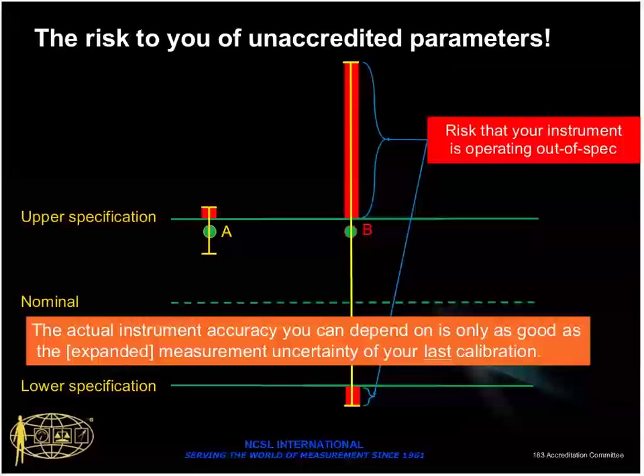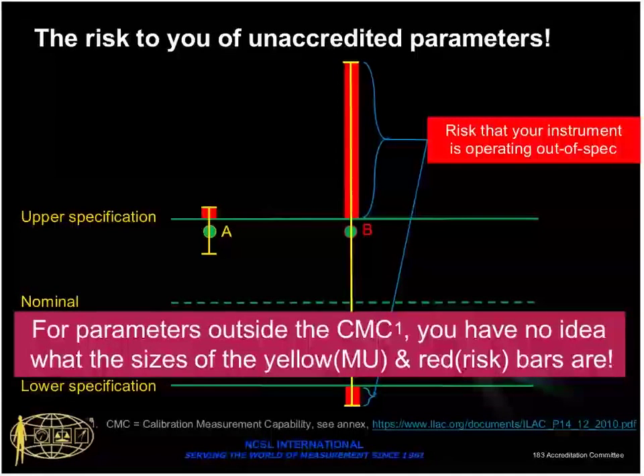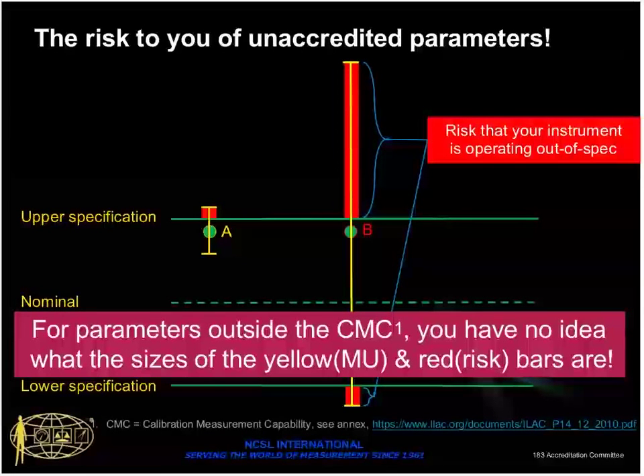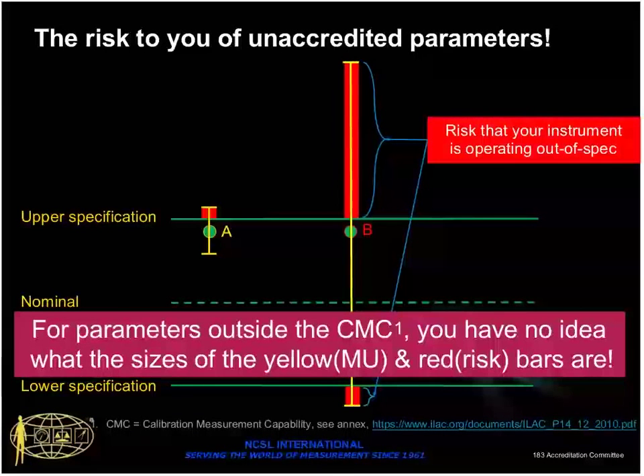Anyway, what I am able to tell you with some confidence is that, I'm afraid, quite often when there is a parameter which is not accredited, the actual measurement uncertainty, although we don't know what it is, would be at least as bad as what we're showing you in case B. So I think what you can say here is that for parameters that are outside the calibration measurement capability or the schedule that Trevor was mentioning just a moment ago, you really have no idea what the size of that risk bar is. The only thing you can say for sure is that it was not assessed.